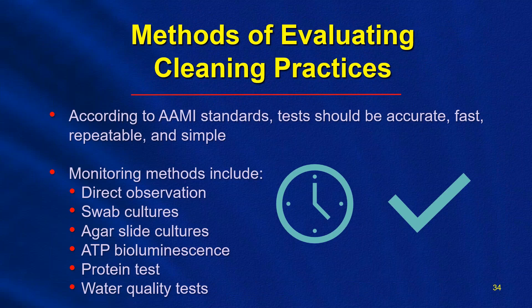So visual inspection can help when gross contamination is visible, but it's not a reliable measurement of any level of cleanliness. Visual inspection cannot detect biofilm or any unseen bioburden. Additional verification is necessary to ensure optimum patient safety, and there are multiple verification methods that can be used as an adjunct to assess cleaning efficiency.